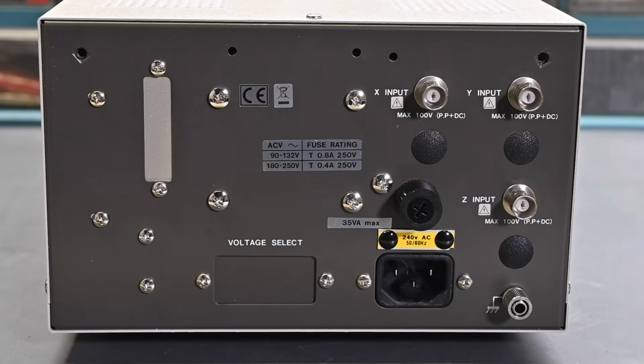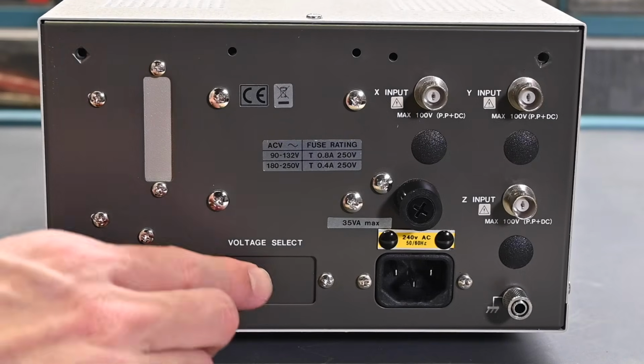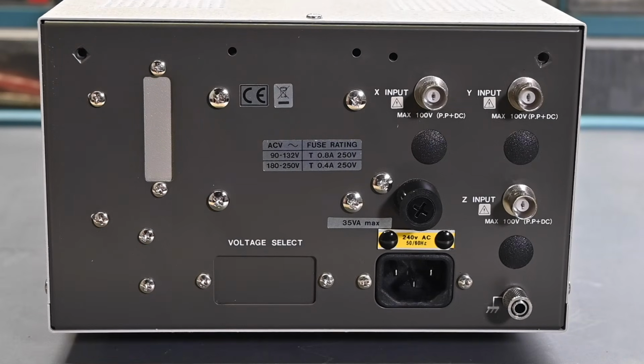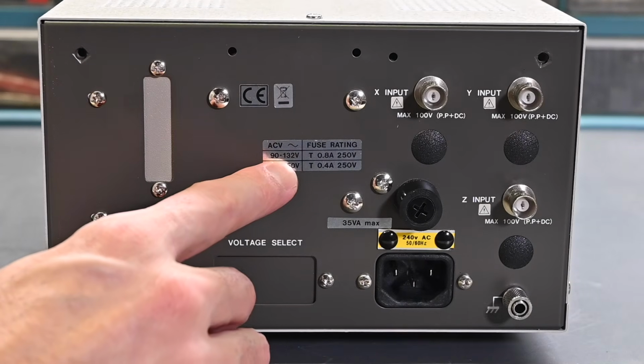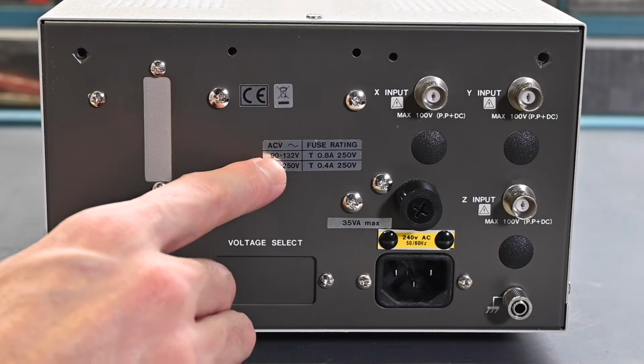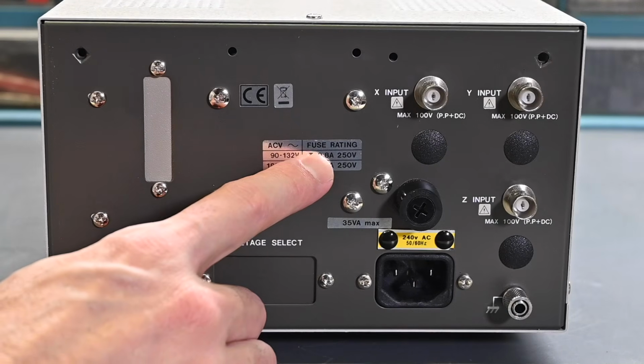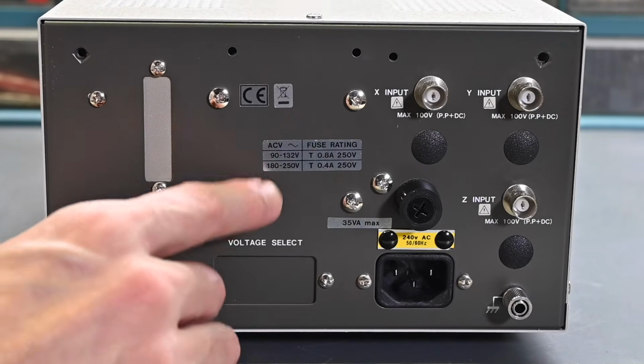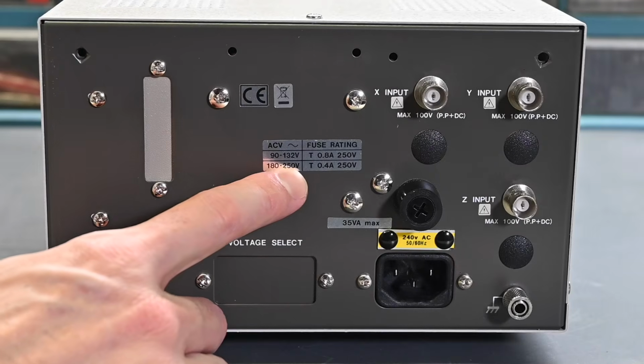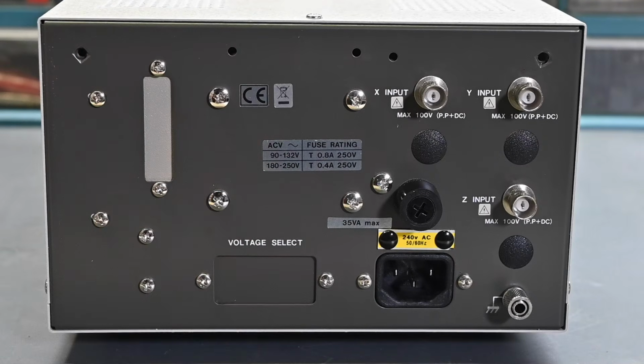Now there's no external voltage selector switch, although the back panel is punched and marked for such a switch. So let's take a look at the fuse rating. There's two different possible fuses depending on the line voltage. So 90 to 132 volts is supposed to be 0.8 amps or 800 milliamps, and then 180 to 250 volts is 0.4 amps or 400 milliamps. So let's see what's actually installed.